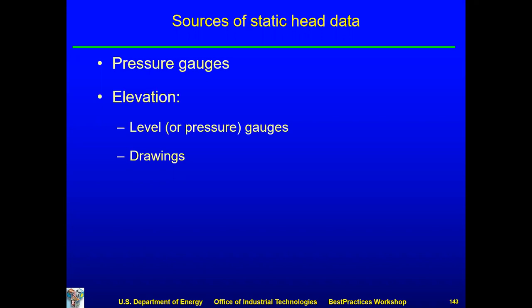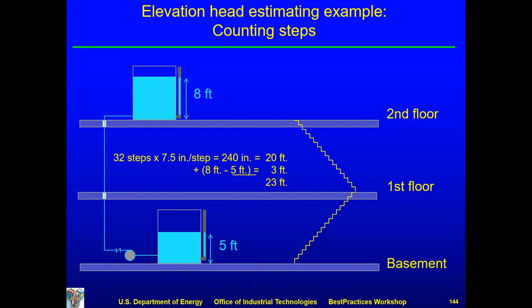Okay. So elevation, we can measure it, we can estimate it, whatever. Here's one way. Sometimes your suction tank may be down in the basement and you're pumping up 6 floors or 2 floors or whatever. Well, you can actually count the number of steps. Somehow you have to find a way to estimate. So we're saying, what? 32 steps times 7.5 inches a step is 240 inches, which is 20 feet. Plus we've got 8 feet. So you want the elevation from free surface to free surface in the tanks. On that second floor, we've got 8 feet of fluid in the tank from the floor. And then, of course, in the basement, we have to subtract off that 5 feet to get the elevation from free surface to free surface.